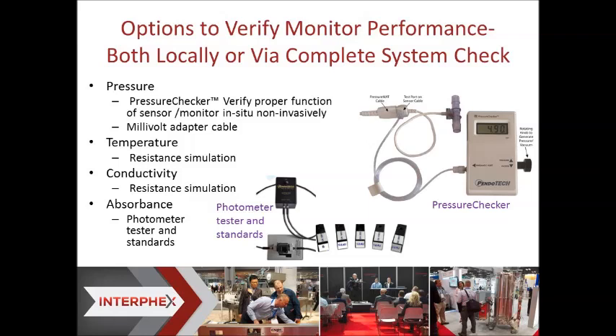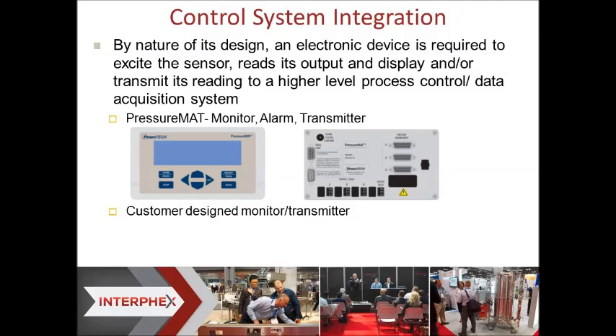In addition, our pressure sensors have a test port where you can actually test the functioning of the sensor and the complete system of the monitor by applying pressure non-invasively to the atmospheric reference port. So temperature, you can simulate a temperature measurement with a resistance simulator. Conductivity, you can measure with a resistance simulator. And for absorbance, to measure the photometer performance, we have a tool here. We can hook the photometer up and a range of these cells get put into the tester, and they perform a non-sensor related performance evaluation of the photometer. And finally is the control system integration.